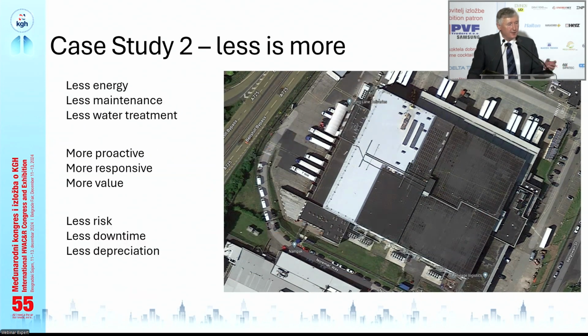Now, the benefit of this is it greatly reduced their energy consumption. It reduced their maintenance requirement. Previously, they basically had somebody attending to the plant permanently, and now it's switched to a visit for a day once a month. And they got rid of the water treatment requirements for the evaporative condensers because it's all air-cooled. The system is now more proactive. It predicts performance requirements.